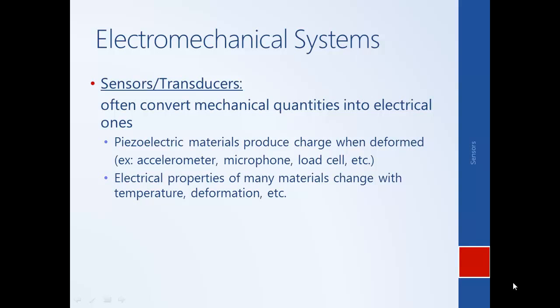Another class of sensor works on the basis that electrical properties of some materials change with mechanical properties. For example, a thermistor works on the basis of its resistance changing with temperature. A strain gauge works on the basis of its resistance changing with deformation or stretching. And pressure transducers generate electrical signals in proportion to pressure based on changes in resistance, capacitance, or inductance depending on the construction of the transducer.